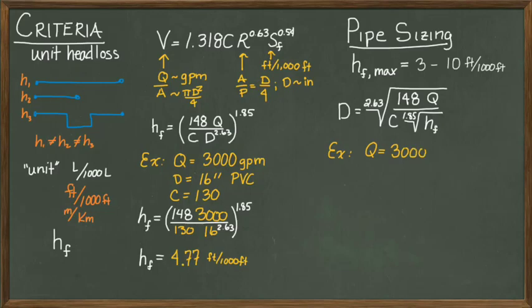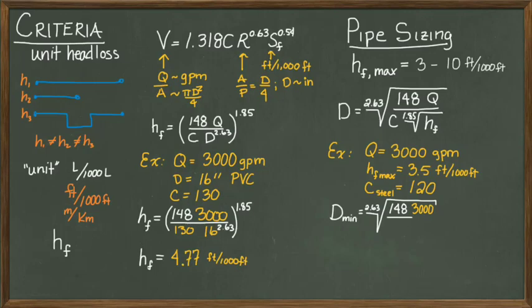Let's suppose we have the same 3,000 gallon per minute flow rate, but this time we don't know the pipe diameter. All we know is that we want to use steel pipe that has a C value of 120. Our new pipe cannot exceed 3.5 feet per 1,000 feet. Plugging in our given values into the equation, we can determine that the minimum diameter is 17.58 inches, which we then round up to 18 inches.